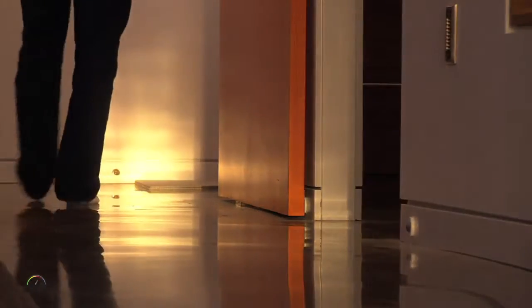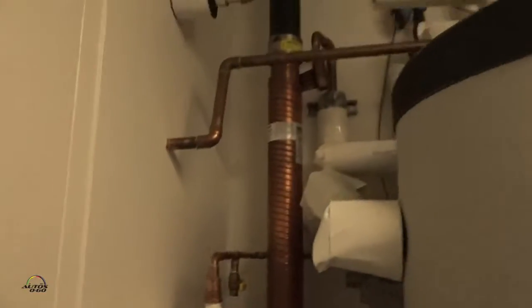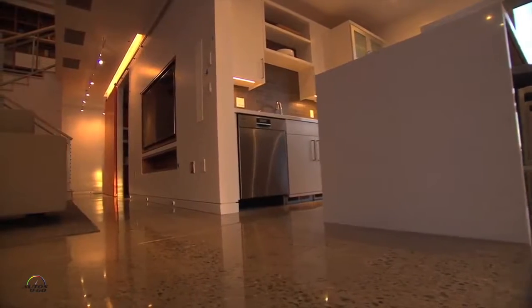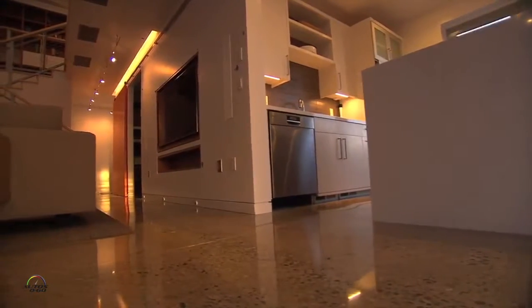So we can heat and cool the house very efficiently, and use the same heat pump to make the domestic hot water very efficiently. Like right now we're making cold water, so we're pulling heat out of the slab. We can actually take that heat and dump it directly into the hot water tank. So today I'm not going to spend any energy on making hot water because I'm making it for free when I'm cooling the house now.